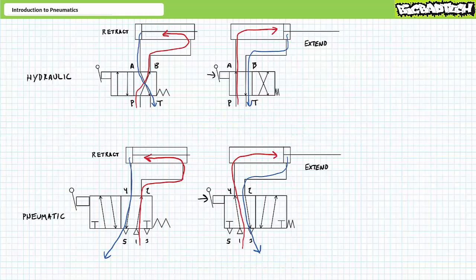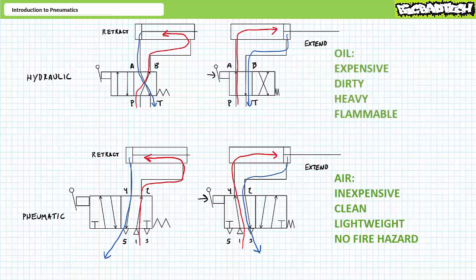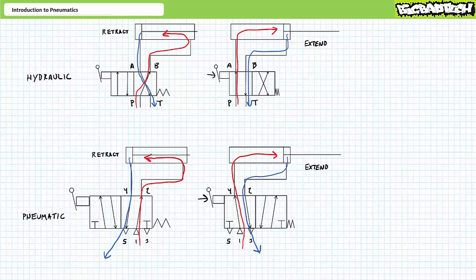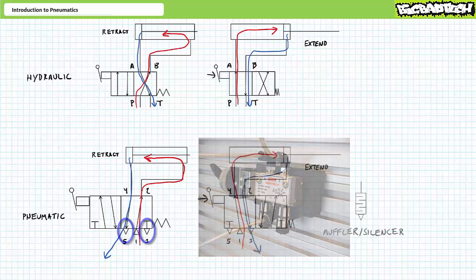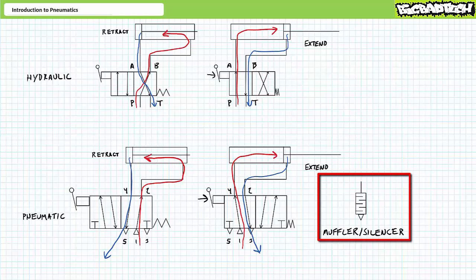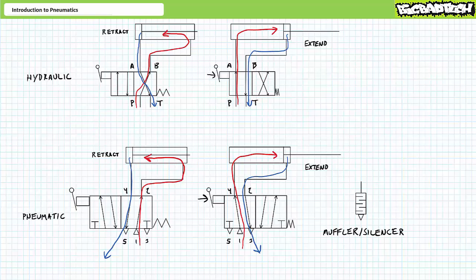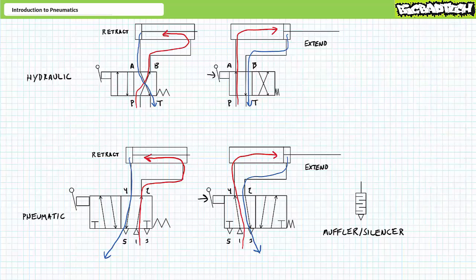Air is clean and free, and you can always get more. This is one of the major advantages of pneumatic systems — the fluid used, air, is cheap, clean, and plentiful given we're quite literally immersed in it at all times. Oil in contrast is dirty, heavy, expensive, and must be contained in a reservoir for continual reuse. This exhausted air expelled into the environment often results in a characteristic hiss every time a valve is shifted. Sometimes you'll see a muffler or silencer intended to minimize this hissing sound. The muffler schematic symbol is a maze-like zigzag passage for escaping air, designed so that exhausted air doesn't experience any undue back pressure.